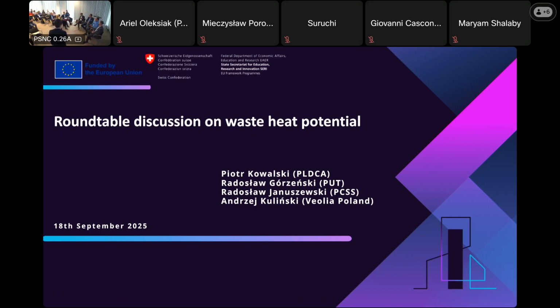Sure, thank you. I'll address the barriers in a second, but first I want to address the data center industry being ashamed of having waste heat of only 40 or 50 degrees. That's an asset, something that can be reused. I think the mistake we're making is thinking of district heating systems as something that operates at 100 degrees. We only have 40 or 50 degrees, so there's no way of matching it. But having a consistent load, a consistent source of waste heat at 40, 50, or even 30 degrees—that is an asset that can be utilized.